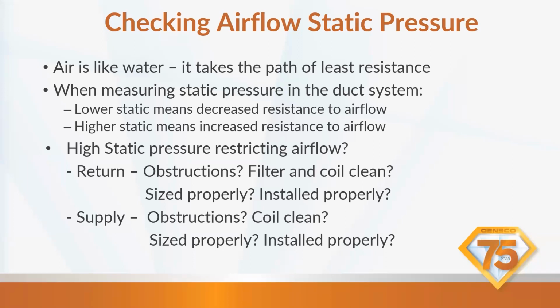I tell everybody and the homeowners, I used to be out in the field, I give my homeowners the hair dryer explanation. If you buy a hair dryer brand new and you run it and you cover that backside of the hair dryer 50%, it'll still work, right? Yes, it will still work, but it will lead to premature failure. The components will die. So I hear a lot, well, this system's been installed for 2 years. I mean, it's been running like that for 2 years. Again, yes, it will run, but it will lead to premature failure, which makes everything look bad, right? So we have to get those return air and supplies sized correctly.